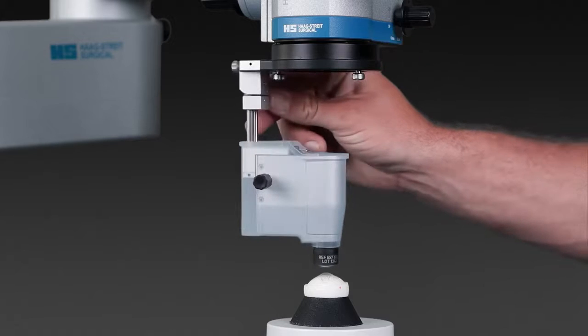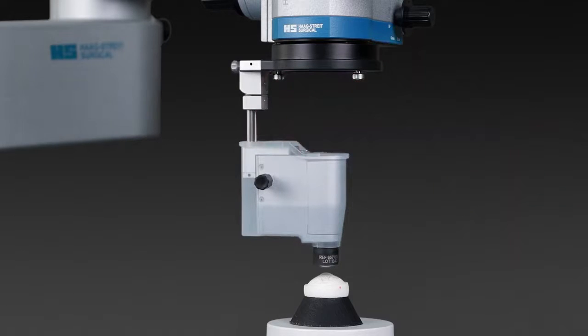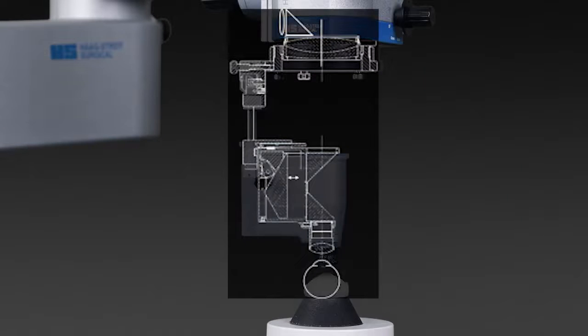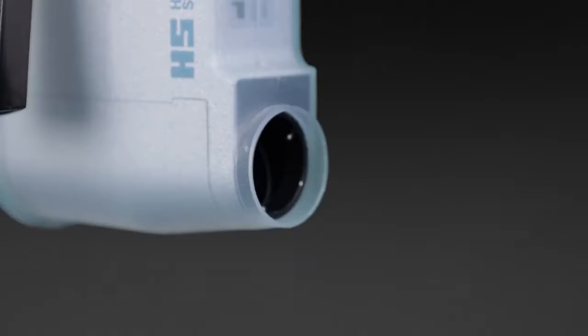The big benefit of the IBIS II is that only one part needs to be mounted and the microscope stays as short as it is. The prism body corrects the inversion automatically within the ophthalmoscopic area.